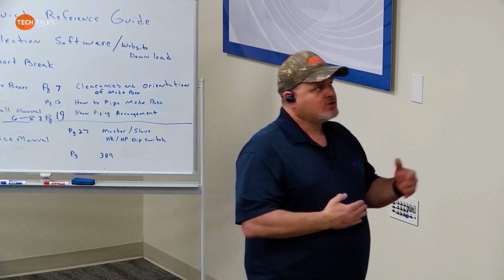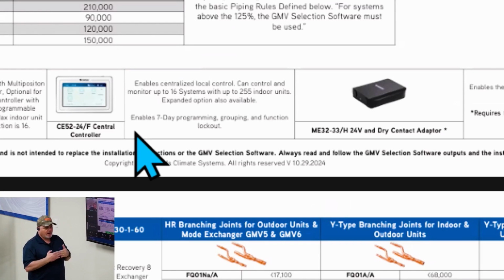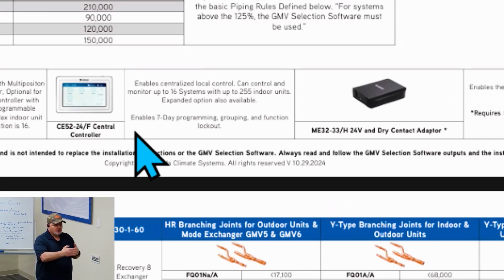If you had just done it ahead of time, the instructions in the central controllers show it perfectly. It shows the wiring, how you daisy chain between G1 and G2 on the outdoor units. You don't have to have your wiring going all the way to the indoor units yet. All you need is your daisy chain between the outdoor units. Before you power them up, you set the outdoor systems. When I say system, if you've got 2 units piped together, that becomes one system, and you're going to have a master and a slave, and we're going to talk more about that. The master's the master. If you have another system, which is 2 units together, that's system number 2, you only set master. System number 3, you only set master, okay? So you set those as unit 1, 2, 3.